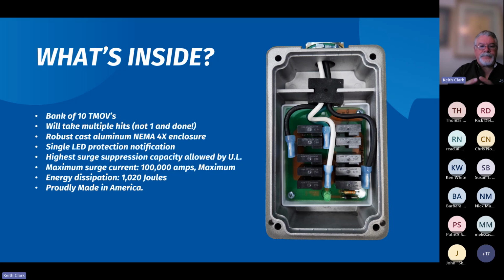Typically, when that surge comes in internally, the TMOV is going to take the hit. It's going to absorb the heat and try to dissipate it off, and it may be able to do that with no damage and then continue to take hits, or it may take a little damage, but still, though slightly degraded, can continue on to take more punishment.